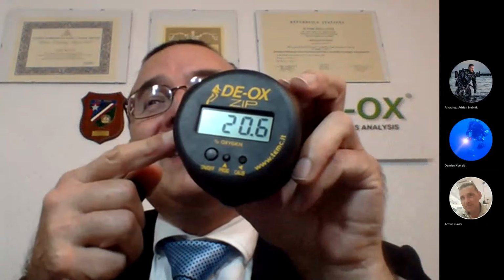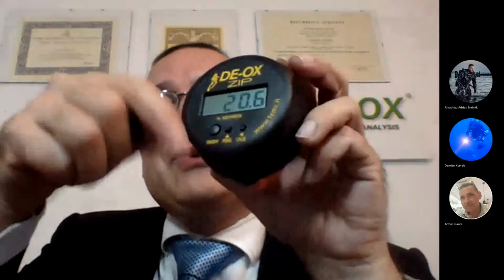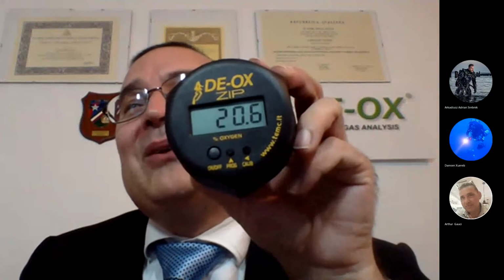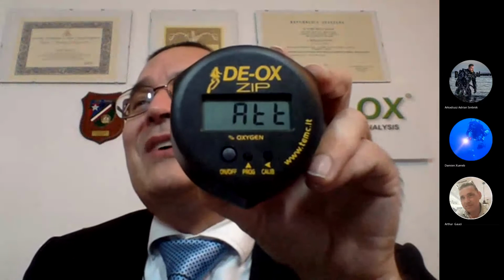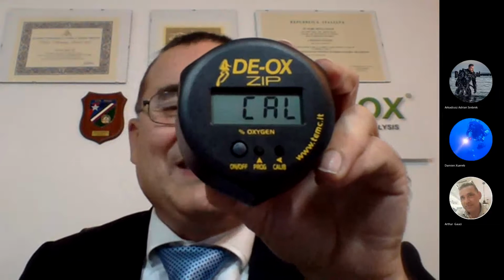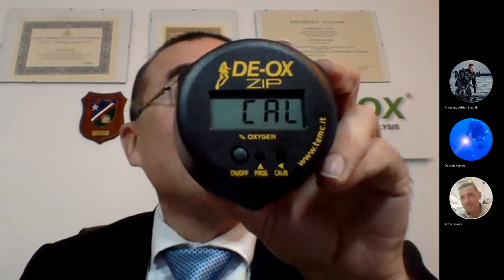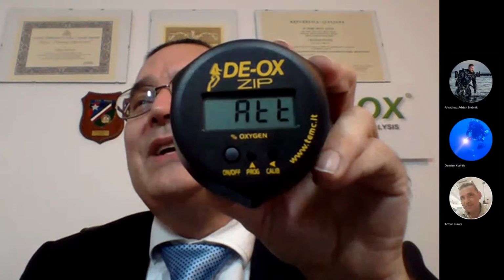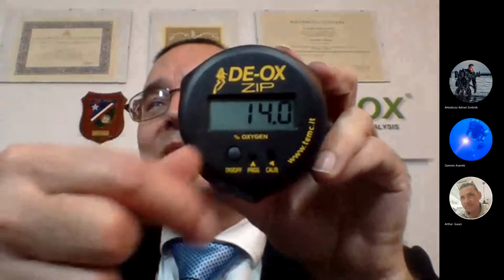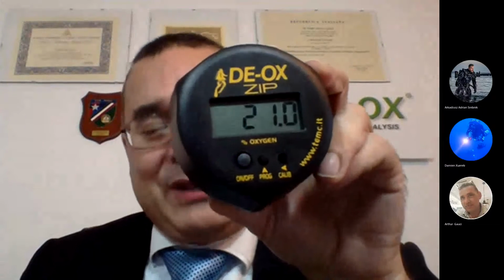Correct, don't use. And you see, now it went to 20.6, it didn't go back to 21 because I calibrated on 99.9, and now we are around 1% of error, below 1% of error. Understand? Now I should take the calibration. Okay, now what I can do is go back to the original calibration of air. I reset the unit, and then it will make a calibration of 21%. Otherwise, I had to turn the screw, the trim, and now I'm at 21%.